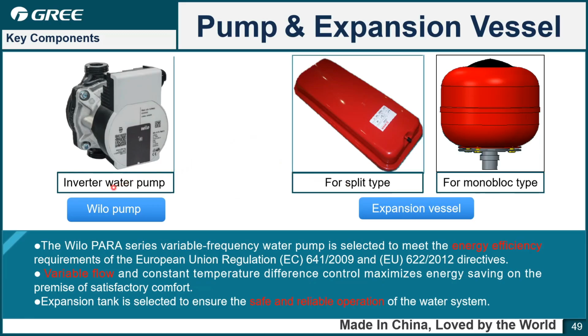And for the pump, it is an inverter water pump, and the expansion vessel. You know, for the VERSATI 3 there are two different types. The first one is for a split type and all-in-one type, which is a rectangular flat one. And for the monoblock type, the expansion vessel is a cylinder, just because of the space in our units, we have to change the size and the shape.